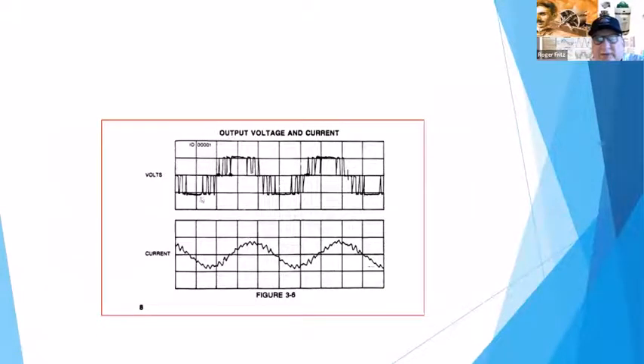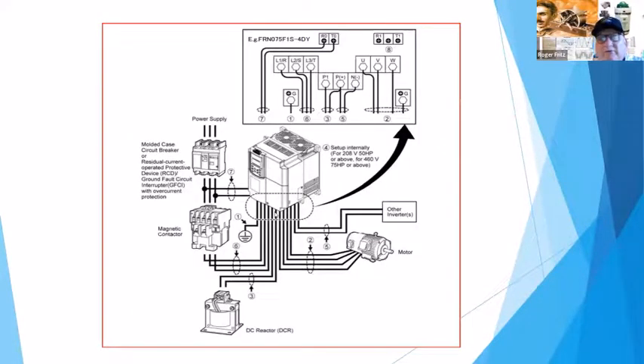And this again was the way the pulsing looked. So you can see the firing on the old GTRs was a lot slower. And you would actually hear the audible noise in the motor. The motor would get a metallic whine to it because you were hearing the frequencies created by this other type of power supply. Again, the current waveform was pretty sinusoidal. And then, over time, it's grown dramatically.